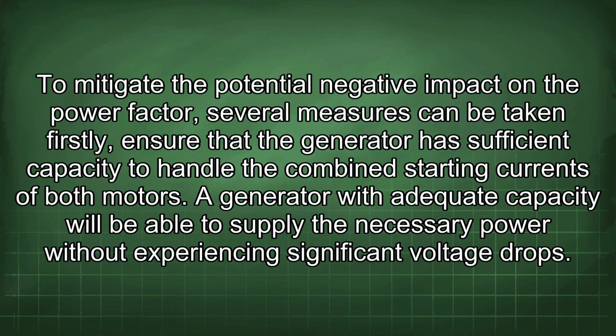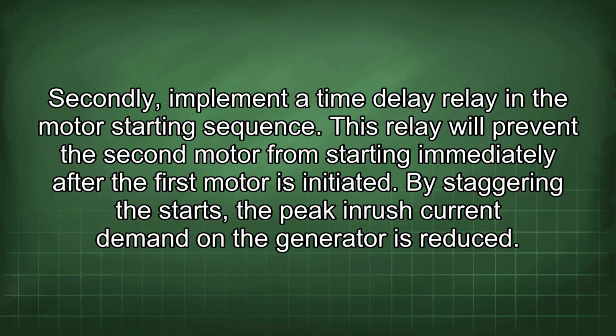To mitigate the potential negative impact on the power factor, several measures can be taken. Firstly, ensure that the generator has sufficient capacity to handle the combined starting currents of both motors. A generator with adequate capacity will be able to supply the necessary power without experiencing significant voltage drops. Secondly, implement a time delay relay in the motor starting sequence. This relay will prevent the second motor from starting immediately after the first motor is initiated. By staggering the starts, the peak inrush current demand on the generator is reduced.